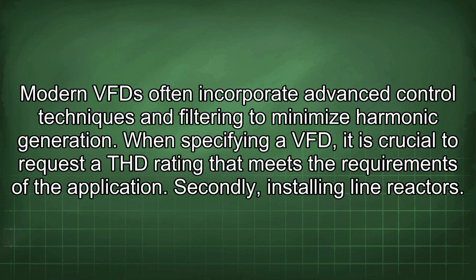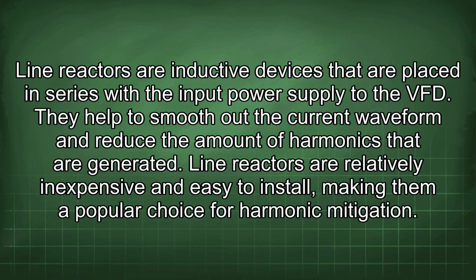Secondly, installing line reactors. Line reactors are inductive devices that are placed in series with the input power supply to the VFD. They help to smooth out the current waveform and reduce the amount of harmonics that are generated. Line reactors are relatively inexpensive and easy to install, making them a popular choice for harmonic mitigation.